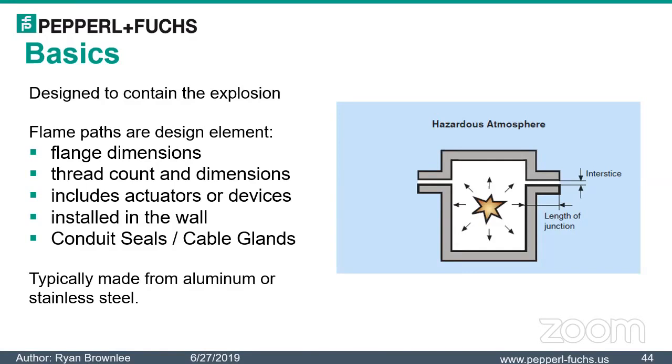And people would do things like put Vaseline on here, or they use copper shield. We got metal particles in here. It's got to be a tight seal. The biggest culprit is they would take this and put it on the deck of a platform, and of course it's rough, so you know, tracking and stuff. They pick it up and they drag it across. I look at it, I said, I don't even want to see that. Oh, we'll just buff that out, or we'll get some steel wool. Guys, you don't understand. This is thousandths of an inch of tolerance.